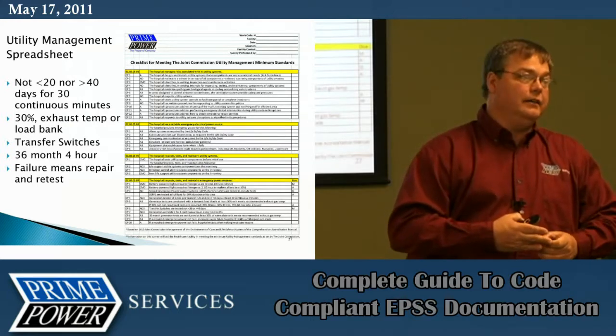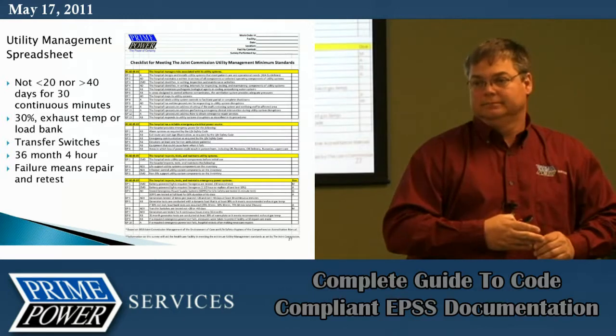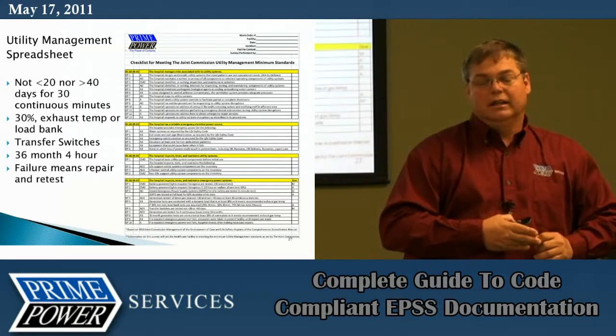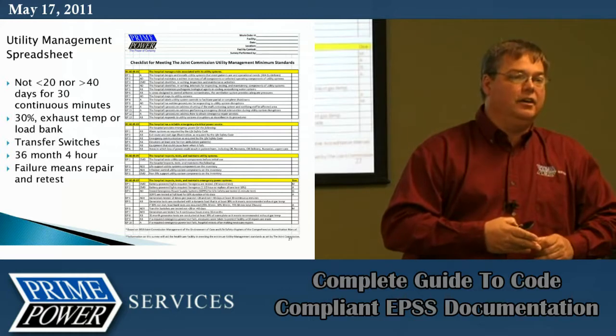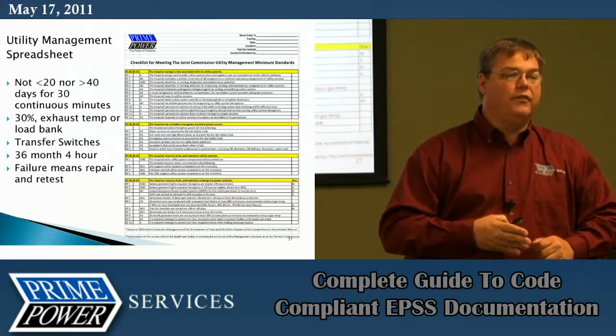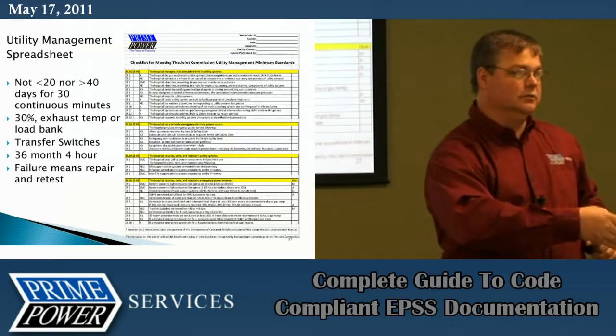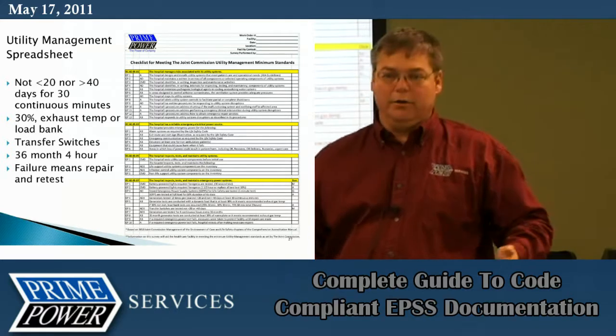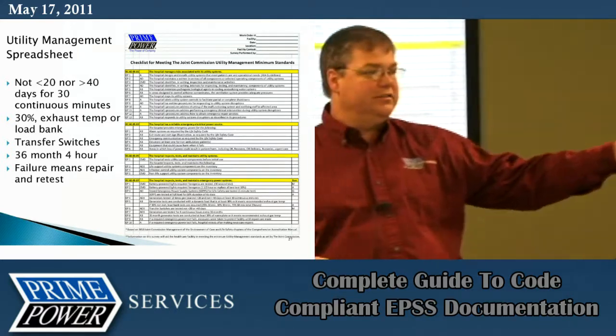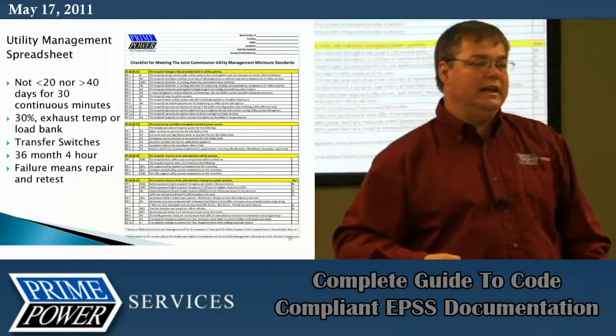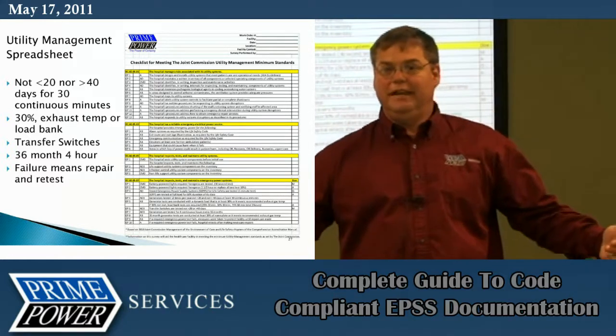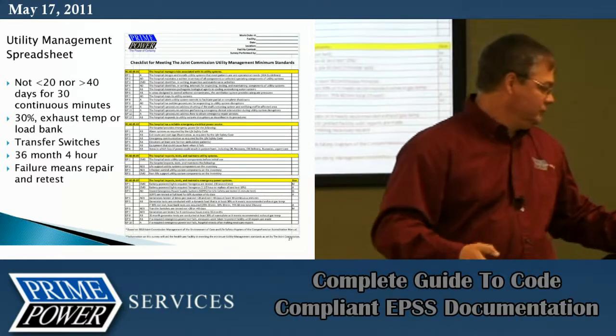So if you cannot, then the recommendation is to get a load bank. You know, sometimes when you look at the life cycle of your generator, it may be better off for you to add something like a chiller so that you can get that load up that you can shed off during an emergency situation. So those are things to look at and consider for the long-term effect and efficiency of your plant.